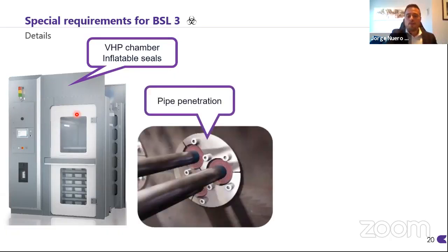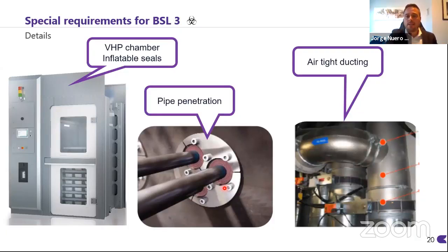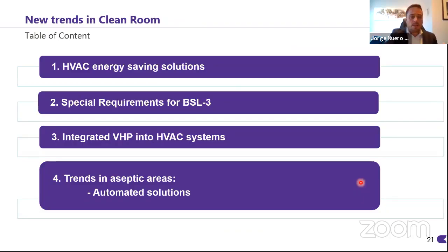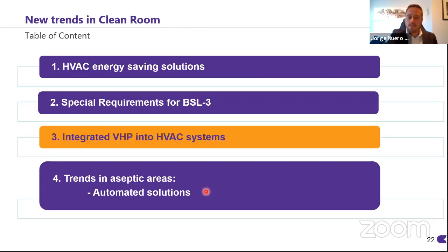Here is how the pipe penetrations look in a biosafety level 3, where we also need to guarantee that there is no leakage around the pipe, or how the airtight ducting looks like. This is a special damper. When we close it, it is totally airtight, so there is no leakage from one side to the other. So it will allow us to make the decontamination of the ducting system as well, as we will see in the next chapter, with VHP decontamination. As I mentioned before, the next chapter is very related with the second one.